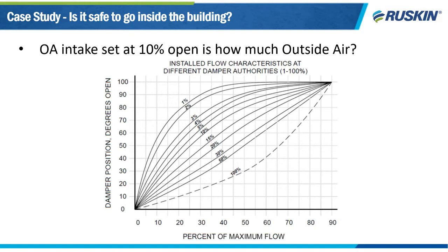A test and balance contractor can come to your building and calculate the percentage of outside air using temperature balancing equations or direct airflow measurements, and will be able to confirm indoor air quality is acceptable by measuring CO2 levels in the building. At the very least, minimum ventilation rates need to be maintained when the building is occupied. Today, more than ever, it's critical to bring in as much outside air as you can to help make your space safe for you and your building's occupants.